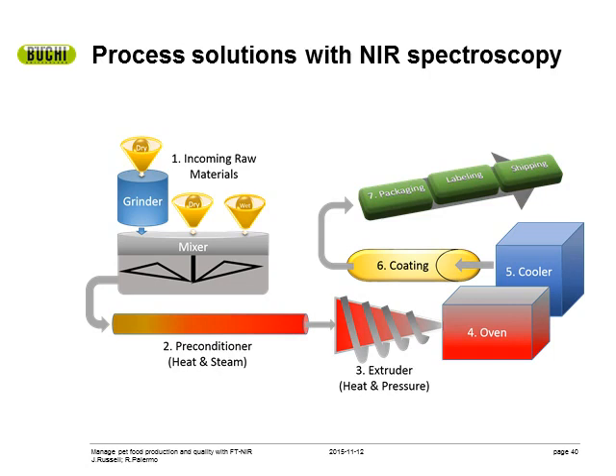Okay, and the second question is, how do you use NIR to identify inorganic raw materials? And the answer to that is that you really shouldn't be using NIR as a primary method for inorganic materials. However, because inorganics do scatter the light, and the spectrum that we get is a combination of both the absorption events and the scattering events that occur when we illuminate a sample, we can sometimes get away with identifying or quantifying even some inorganics in an organic matrix, but it's not necessarily something that we would be approving.